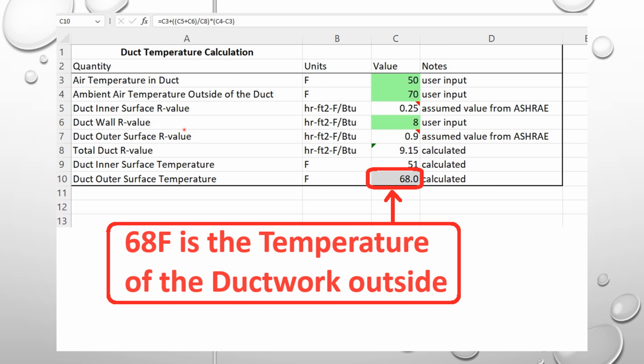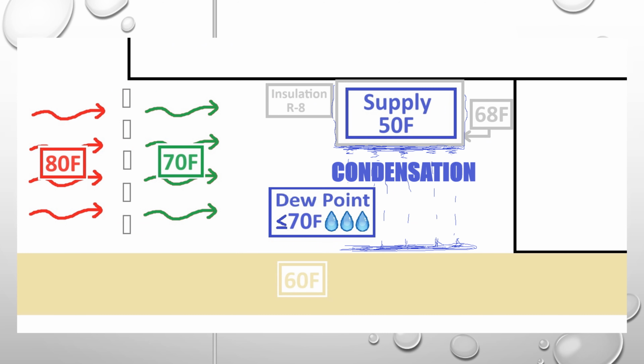In our R value, we wrapped the ductwork with R8, and this all formulates and ends up showing us that the duct outer surface temperature, which is extremely important, this is what I was trying to find, the temperature of the outside of our ductwork, is 68 degrees. On the next page, you're going to see what happens when you have a 68 degree object in a dew point that is set to 70. That 68 degrees is colder than the 70 degree dew point, which will condensate.